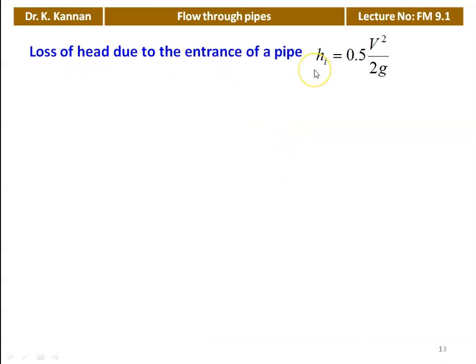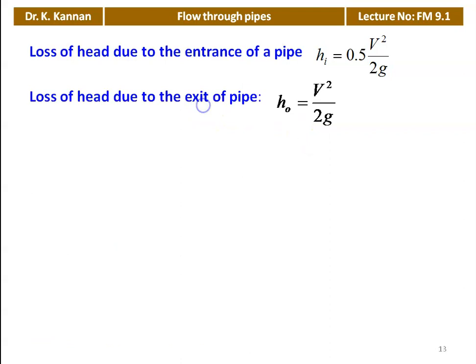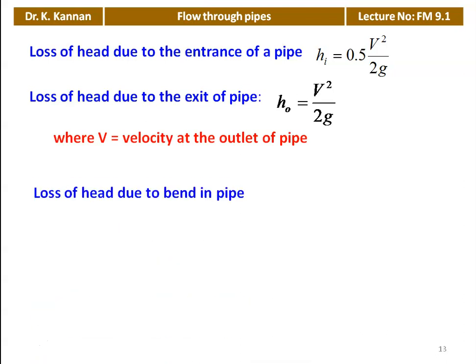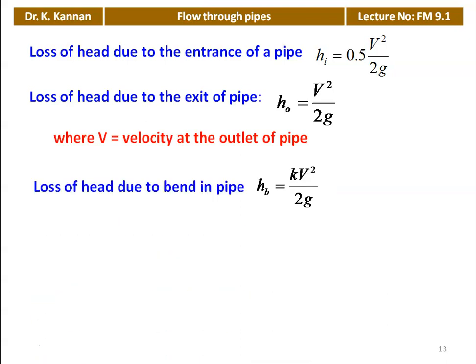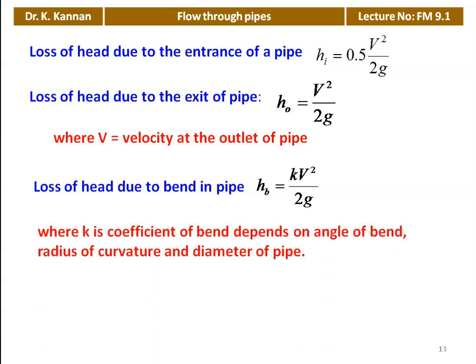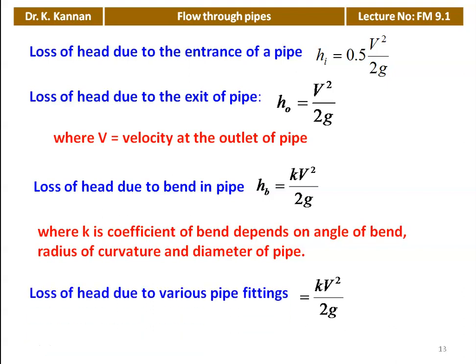Loss of head at the entrance of the pipe: HI = 0.5·V²/2g. Loss of head at the exit of the pipe: HO = V²/2g, where V is the velocity of the outlet pipe. Loss of head due to a bend in the pipe: HB = K·V²/2g, where K is the coefficient of bend, depending on the angle of the bend, radius of curvature, and diameter of the pipeline — the K value will be given in the problem. Loss of head due to various pipe fittings: K·V²/2g, where K is the coefficient of pipe fitting.